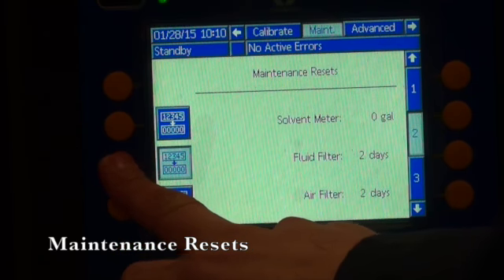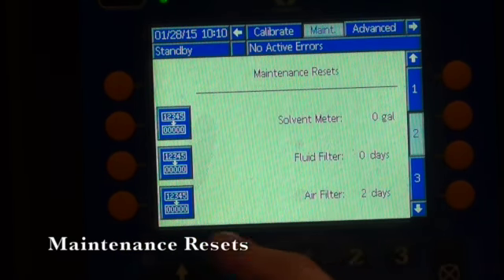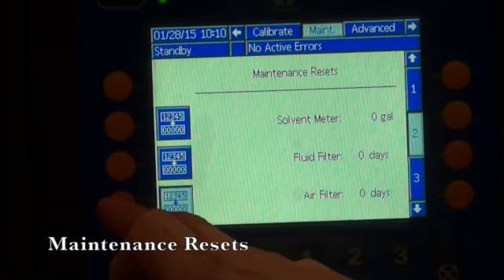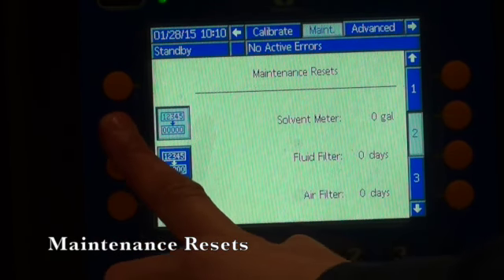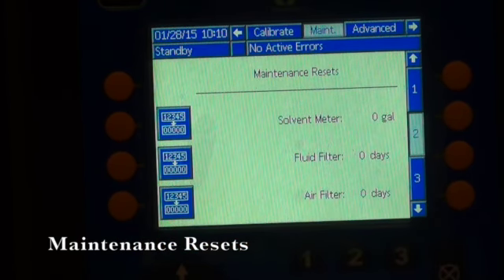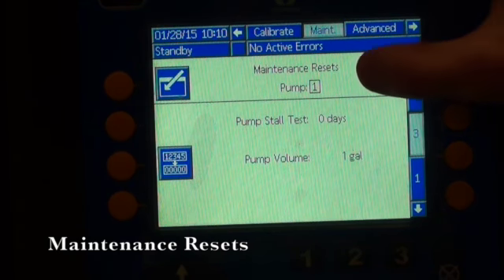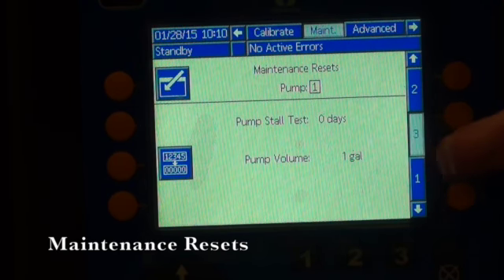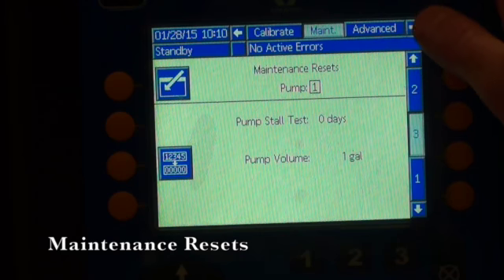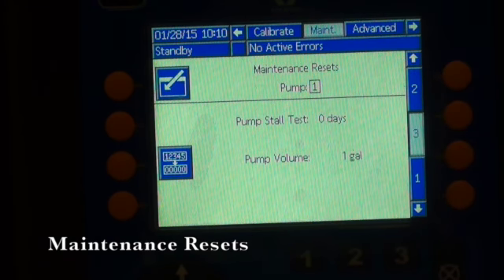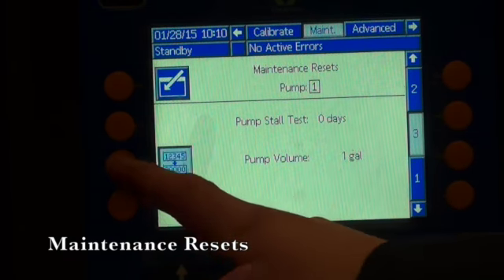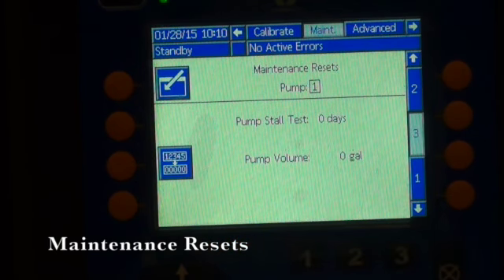The next screen, if you push down on the maintenance, this is where you reset them. Your fluid filter, you just hold the button, resets it. Same with air filter, and the solvent meter was just reset. Down again, you reset each pump, how much volume it's done. So if you get your reminder that you need to change pumps, you can pop your old pump out, put a new one in, and you just go to this screen to reset it.